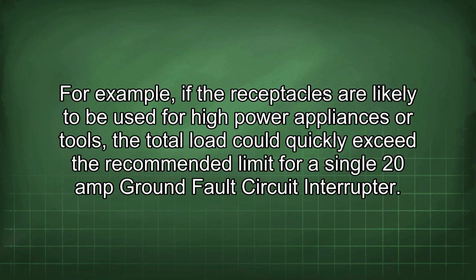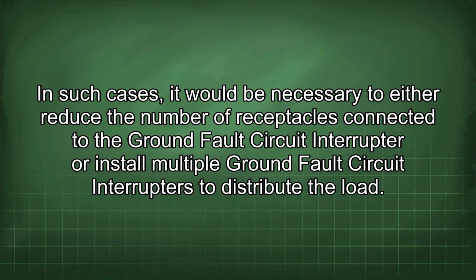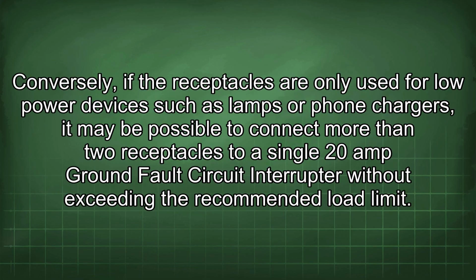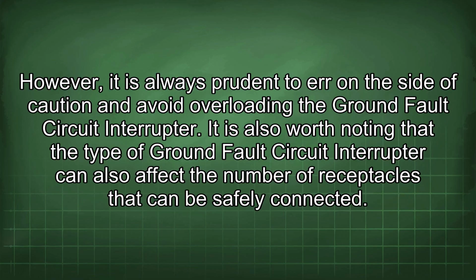draw. For example, if the receptacles are likely to be used for high-power appliances or tools, the total load could quickly exceed the recommended limit for a single 20-amp ground fault circuit interrupter. In such cases, it would be necessary to either reduce the number of receptacles connected to the ground fault circuit interrupter or install multiple ground fault circuit interrupters to distribute the load. Conversely, if the receptacles are only used for low-power devices such as lamps or phone chargers, it may be possible to connect more than 2 receptacles to a single 20-amp ground fault circuit interrupter without exceeding the recommended load limit. However, it is always prudent to err on the side of caution and avoid overloading the ground fault circuit interrupter.